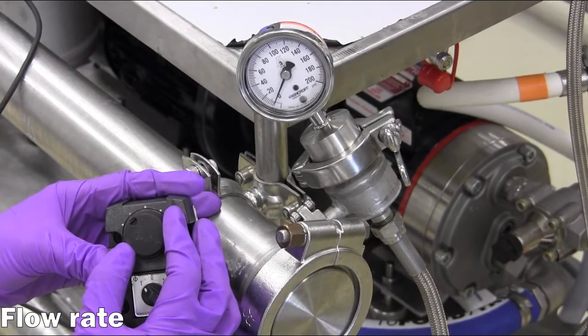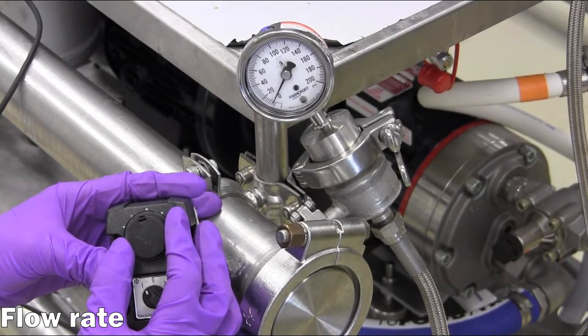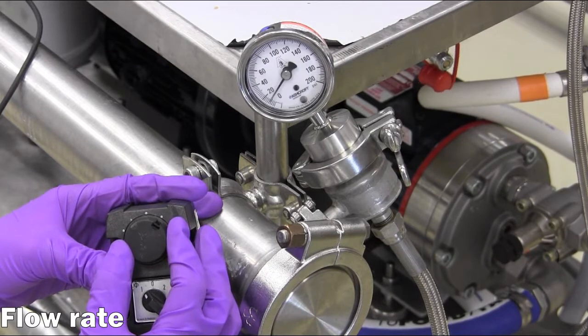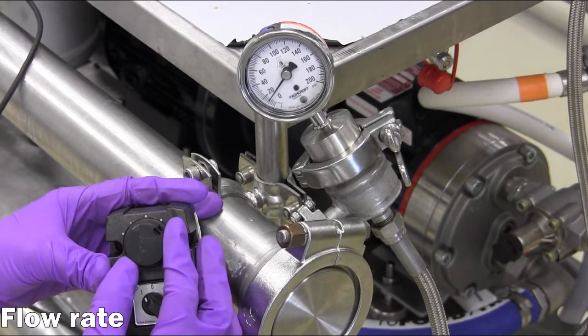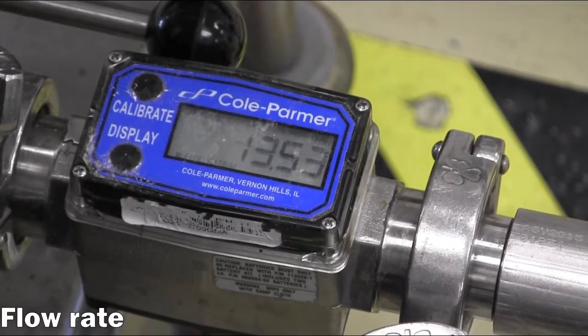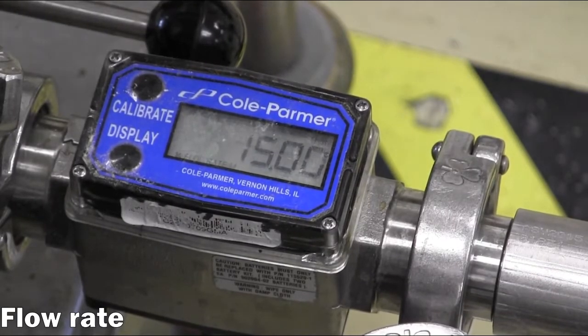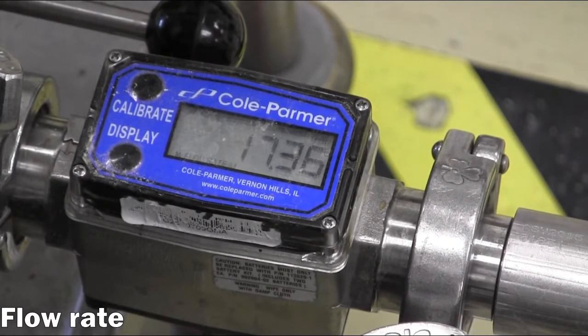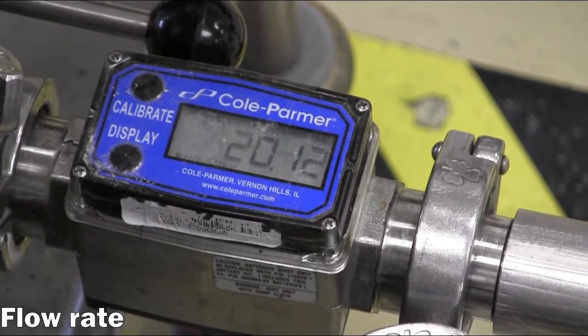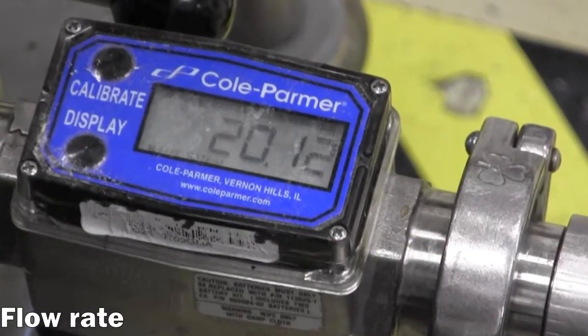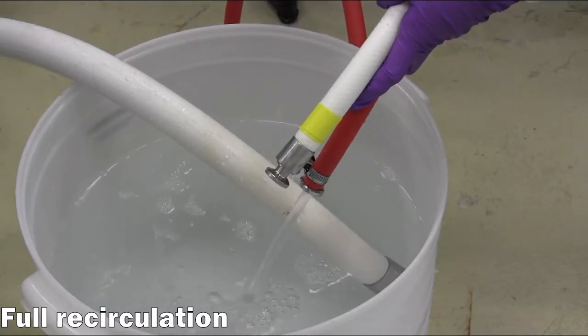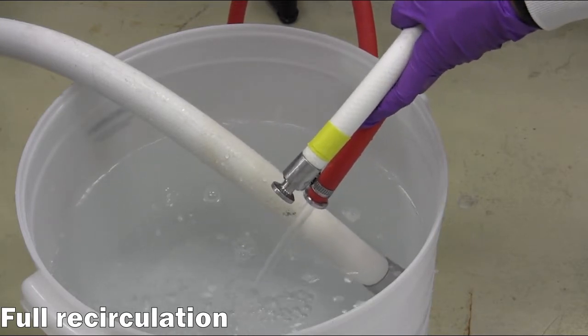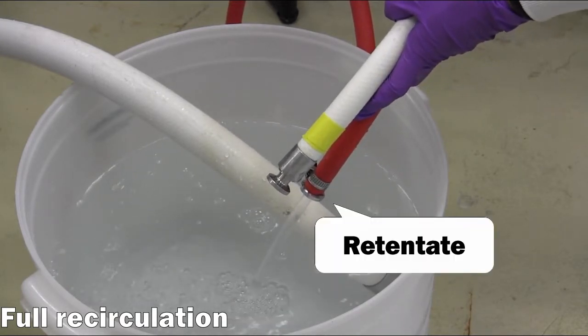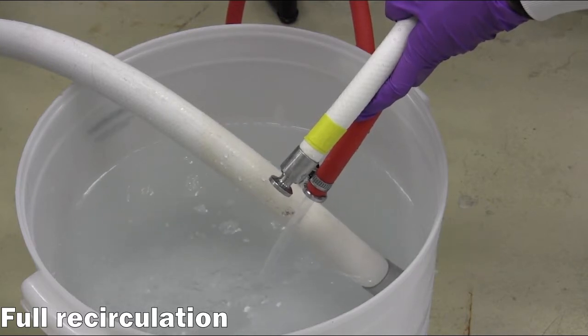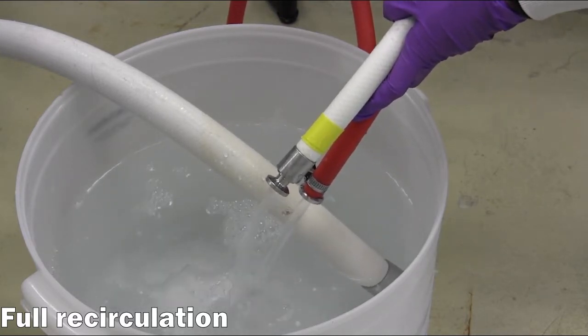A knob may be used to increase or decrease the pump speed, corresponding to the feed flow rate and inlet pressure. The flow rate can be monitored via the digital flow meter near the feed inlet port. Take care to monitor the inlet pressure while adjusting the flow rate to not exceed manufacturer specifications, which may damage the membrane. Continue to monitor the streams as the system runs in full recirculation mode for at least 10 minutes to ensure that there are no leaks and that the system is fully primed with liquid.